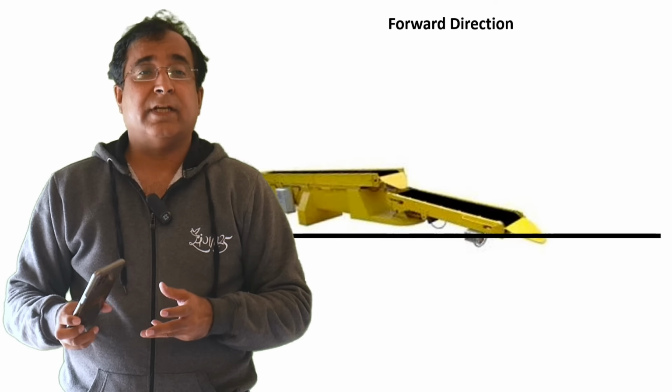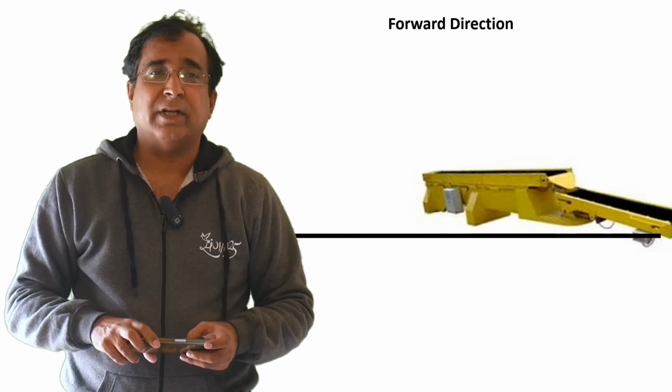When a VFD is installed in a trolley drive like stacker climber, truck loading machine, wagon loading machine, which moves back and forth, forward reverse, it is just to give smooth startup to the machine to avoid jerky movement, which we encounter with forward reverse contactor deployed in the panel. Once I faced a similar situation in a truck loading machine which used to run in forward and reverse direction, okay, with no issue. One day I found in the middle of reverse travel, the VFD is getting tripped due to DC bus overvoltage, particularly in reverse direction. It was not getting tripped in forward direction.